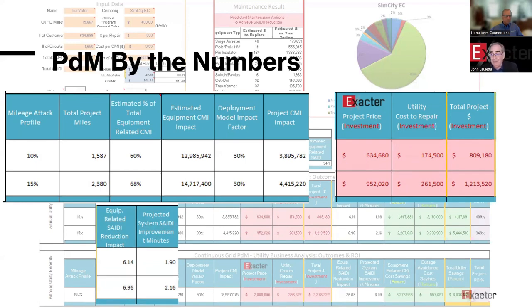Typically, our customers tell us a CMI minute is worth something between 50 cents and $1.25. A SAIDI minute, though, may be $500,000 to $2 million of value. So these are real numbers that have a real impact on the cost performance of the utility. And as a result of that, in a 10% profile, this SimCity utility would have an ROI of the project of over 400%.